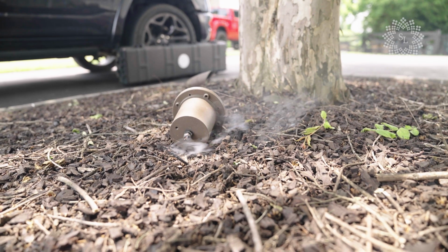So we actually had the transformer come back with an overall good rating. Great, so that was nice. The wiring overall was good, though there were a couple spots where it wasn't buried as well. The fixtures are all older. A number of them had let moisture in, they had deteriorated, and didn't have electricity to them. We had 2 of them that actually caught fire when we were out there.